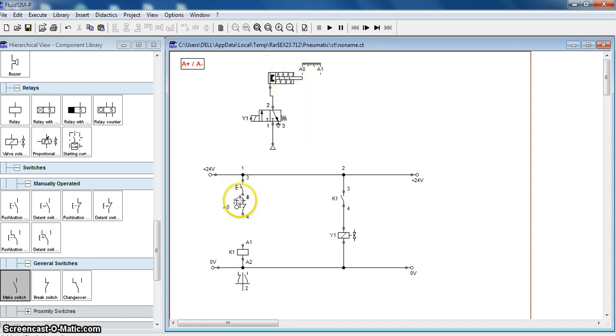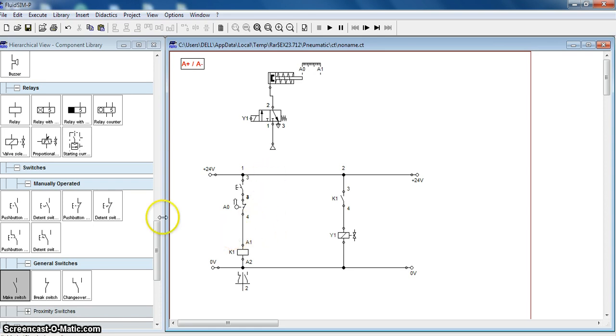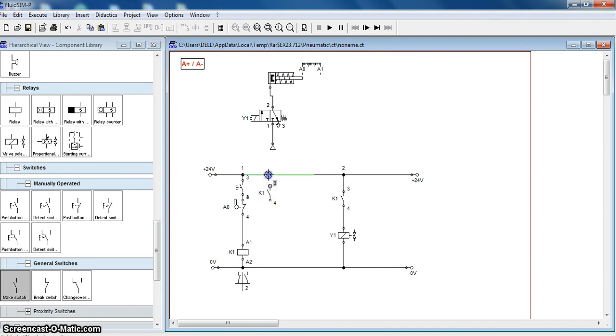When we press the push button, the cylinder is already retracted, so A0 is allowing the current to flow through the push button. This A0 will energize K1. If connected like this, K1 will get energized. When K1 gets energized, its normally open contact will get closed and Y1 will get charged. But if we release the push button, K1 will get deactivated, so we will have to put a latching contact for relay K1. We will put K1 here as a latching contact.